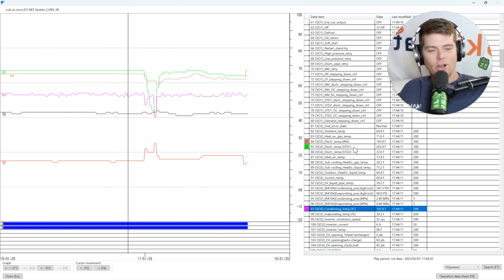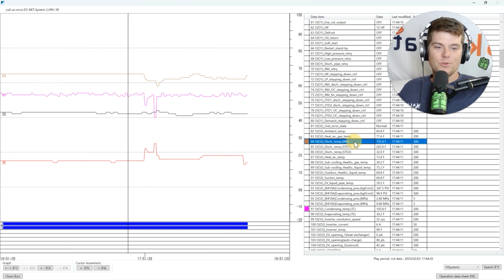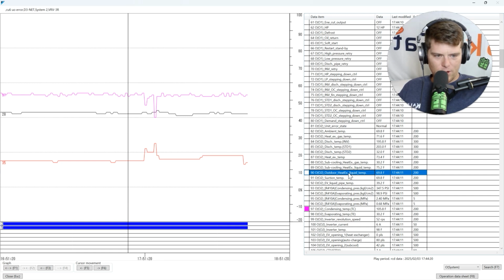That's not terrible. That is terrible. That's awful. 56 degree suction superheat, high discharge superheat. And then guess what? It's even low subcooling. Okay, let's see the subcooling here. Outdoor heat exchanger liquid temp. Where did we go here?